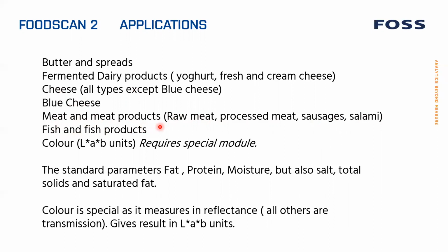Fish and fish products. And now the odd one is color. This is something new. This requires a special module. As I said before, color is typically measured in reflectance. FoodScan is working in transmission. So if you want to do color, you need to add an extra detector. So it will then have a reflectance detector. So you can actually get the color to see if your meat is red or if it's gray, or your blue cheese is blue.